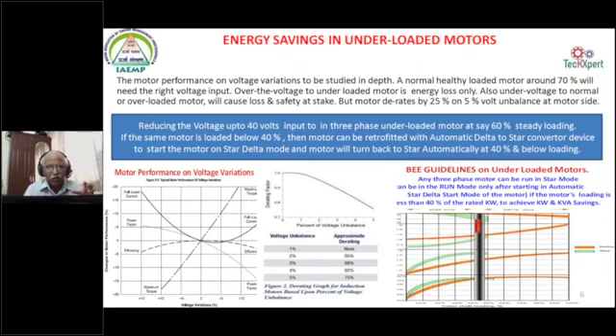And if the motor has a wild, zigzag fluctuation, let us say it's a compressor having a load-unload operation at 7 bar. I have a 50 HP motor, a 37 kilowatt motor, operating from load to unload between 20 kilowatt and 40 kilowatt. It has a big zigzag. Then you need to have the variable frequency drive. Where that is applied and how it is applied through closed loop control will give savings, but that is costly, but the savings are more.